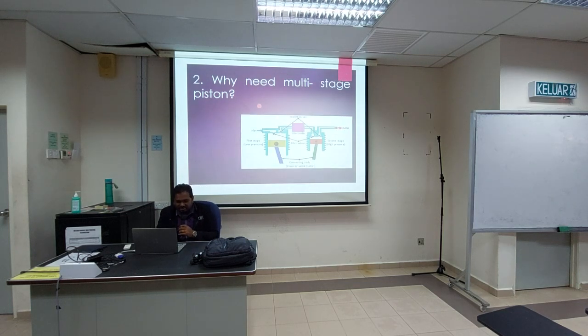Okay, second question, why need multi-stage piston? Kenapa perlukan multi-stage piston? To increase the pressure. Okay, kalau single stage piston, dia cuma boleh up to 7 bar. So multi-stage piston 4 stage, maksudnya ada 4 piston, so it can go up to 250 bar. So yang ni dia bergantung kepada application you.